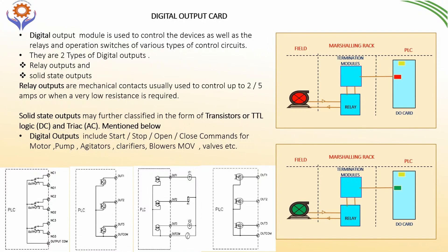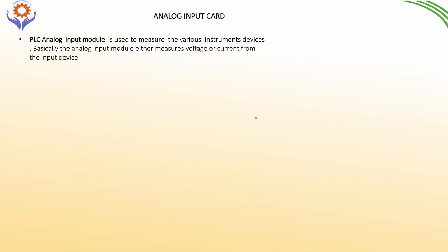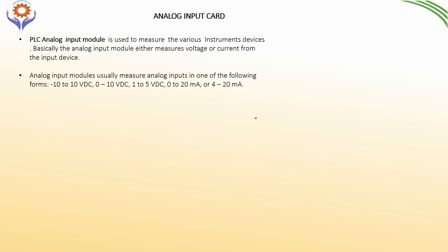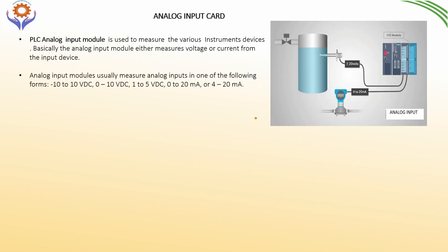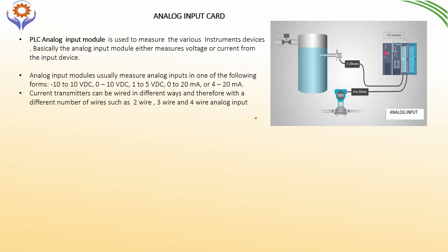The other important I/O devices are analog input devices. The PLC analog input module is used to measure various instrument readings. Basically, the analog input module measures either voltage or current from the input devices. Analog input modules usually measure the analog input in one of the following forms: -10 to +10V DC, 0 to 10V DC, 0 to 20 milliamperes, or 4 to 20 milliamperes. For major industrial instruments, they typically use 4 to 20 milliamps — why we use 4 to 20 milliamps will be covered in a separate class.